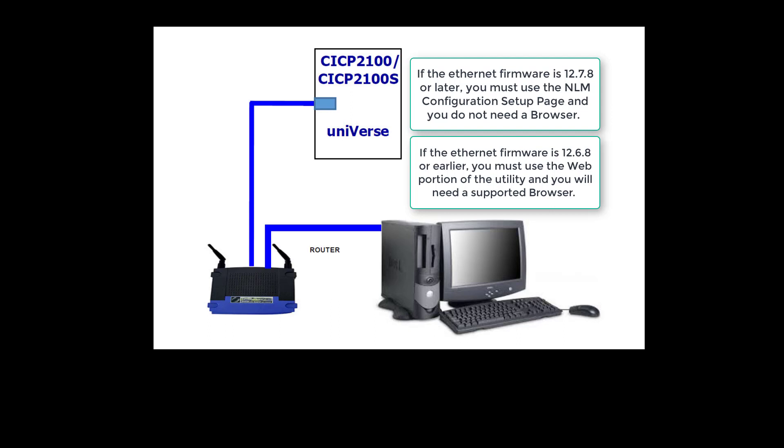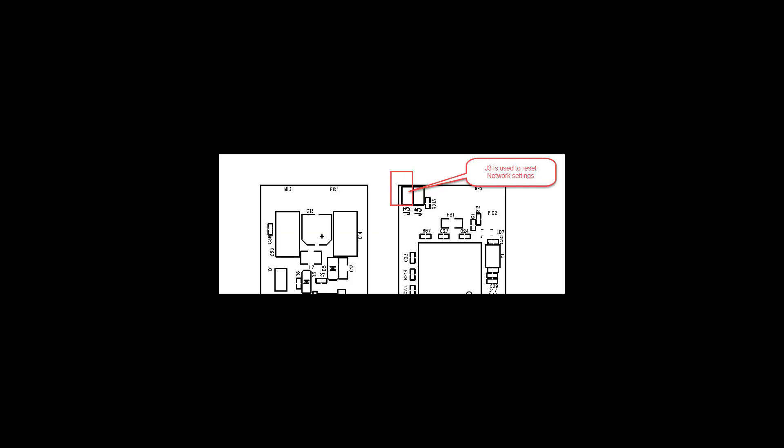By default, the CICP-2100 and CICP-2100S will be configured to DHCP mode when purchased. If there is any previously programmed IP address information already programmed in, it is recommended to reset the unit. To reset the CICP-2100 and CICP-2100S back to the default network settings, you must install a jumper — apply a short across the J3 jumper on the Ethernet interface board while cycling power to the unit. This will default the network adapter back to DHCP mode.